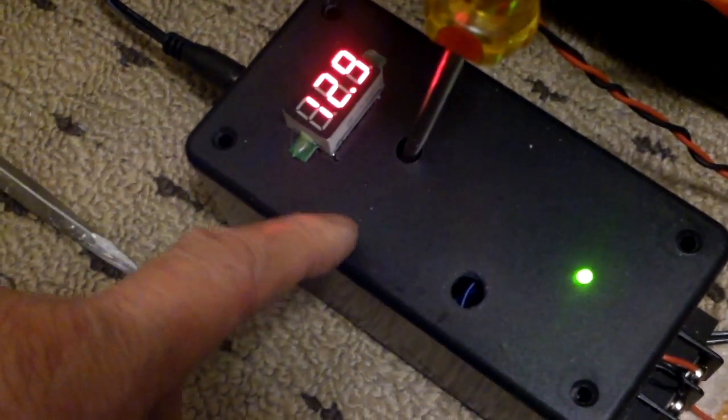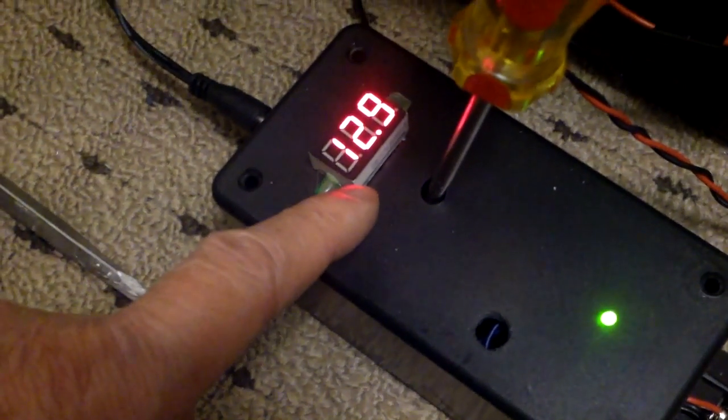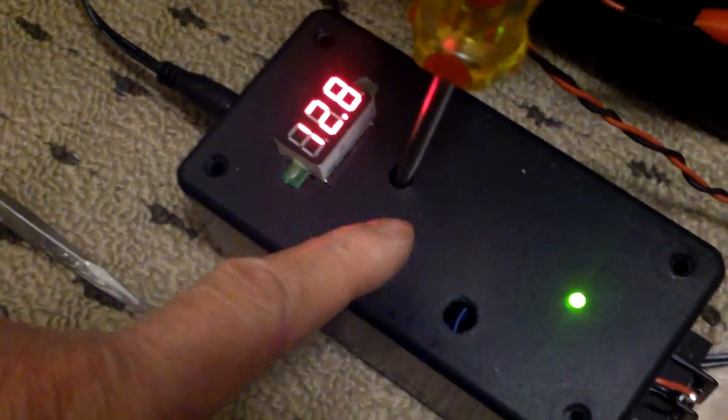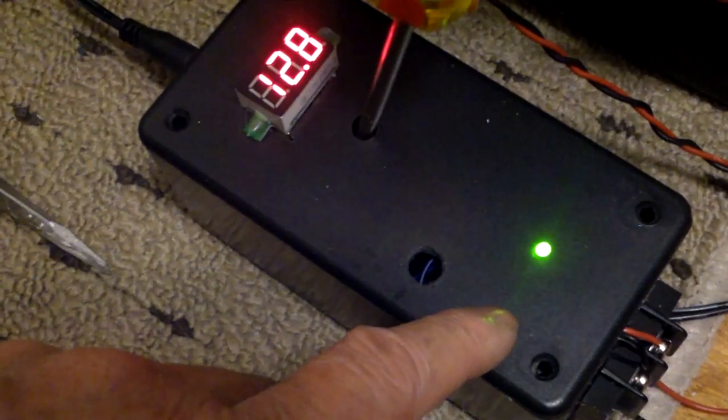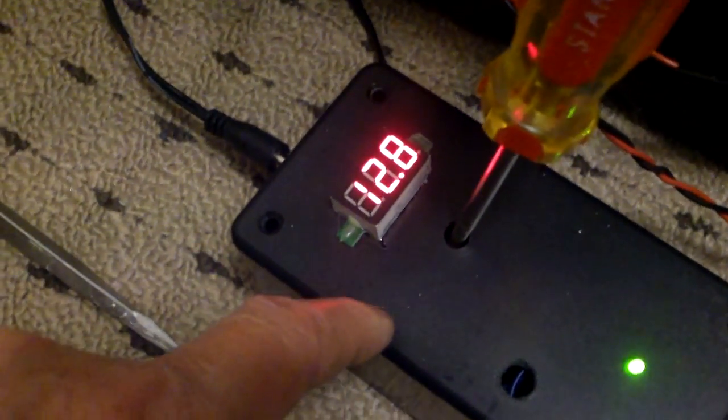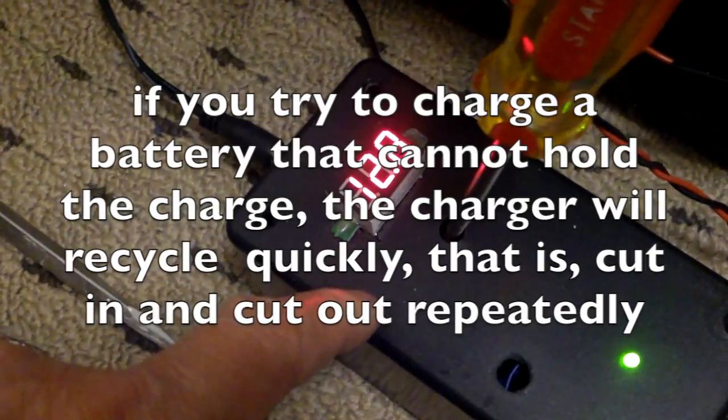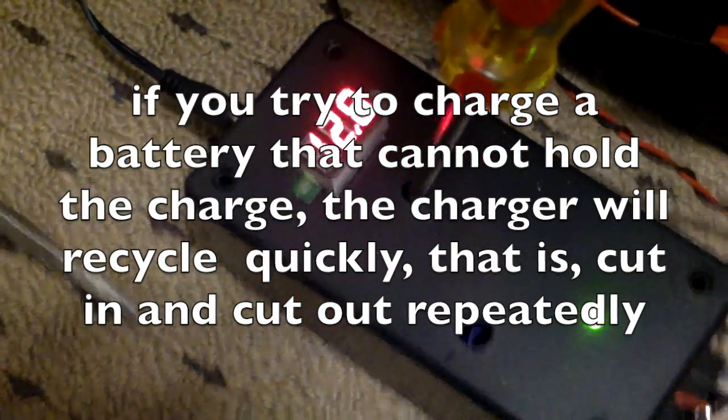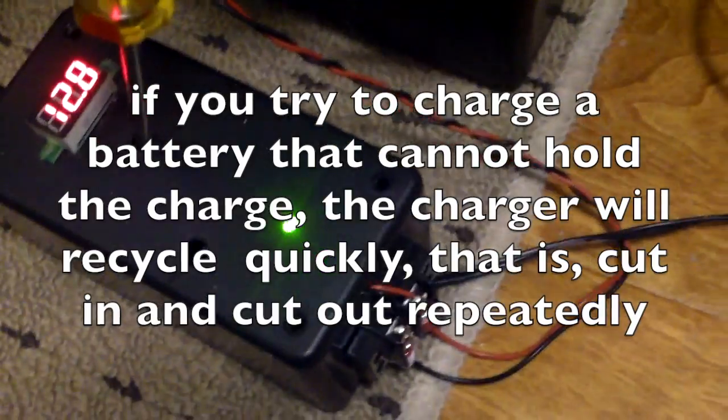You can see that it is cutting in and out. It starts to cut in at about 12.8 volts, the light goes out, and then the voltage goes up to 13.6 volts or so and then it stops charging.